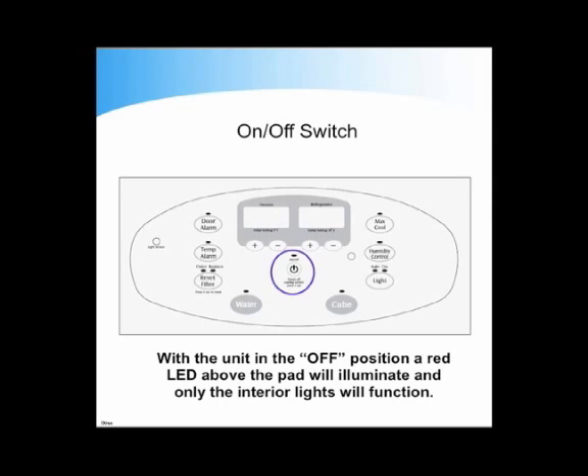Prior to turning off the UI, the current user settings will be stored in EEPROM to be able to recover the customer settings in case of an electrical reset. Certain text or phrases must be shown on the keyboard. This includes cooling on-off, which per UL standards describes the loads which will be turned off by that switch. The phrase also lets the customer know that this button will turn the unit back on.